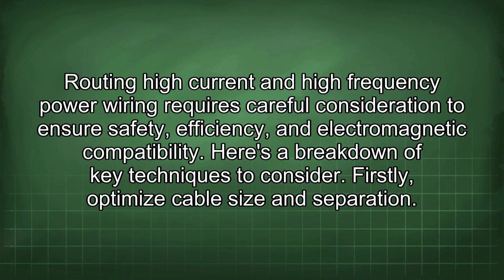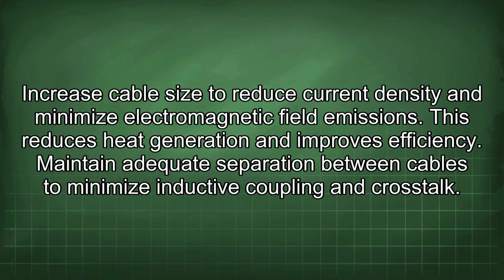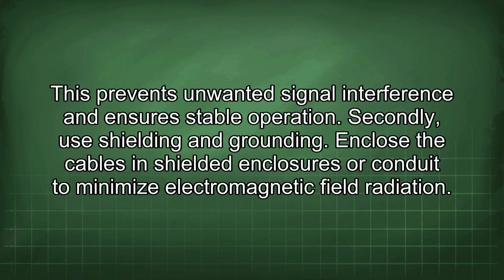Routing high current and high frequency power wiring requires careful consideration to ensure safety, efficiency, and electromagnetic compatibility. Here's a breakdown of key techniques to consider. Firstly, optimize cable size and separation. Increase cable size to reduce current density and minimize electromagnetic field emissions. This reduces heat generation and improves efficiency. Maintain adequate separation between cables to minimize inductive coupling and crosstalk. This prevents unwanted signal interference and ensures stable operation.